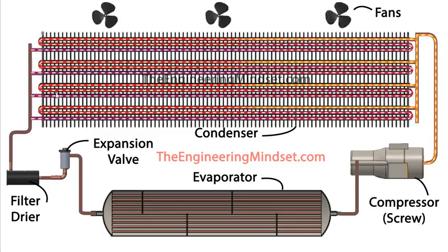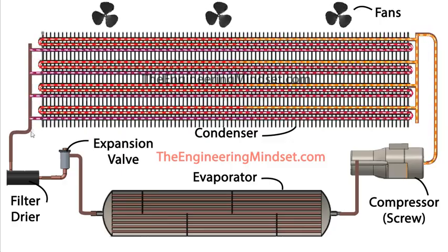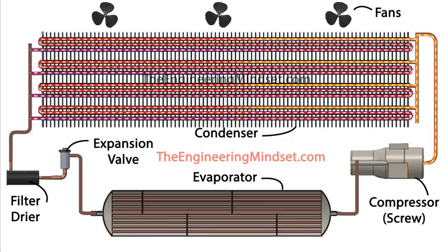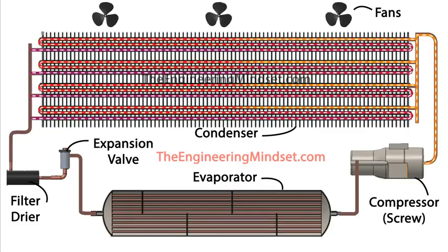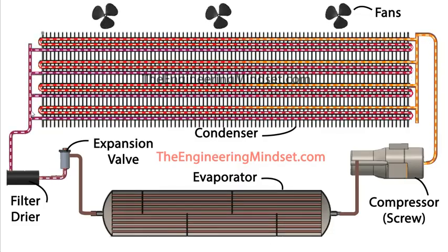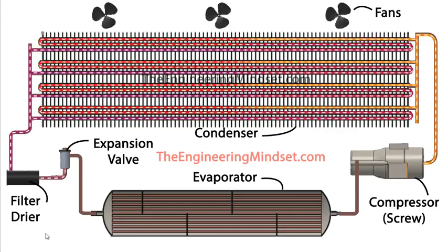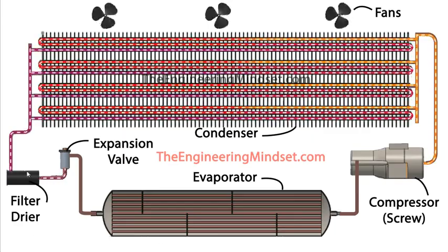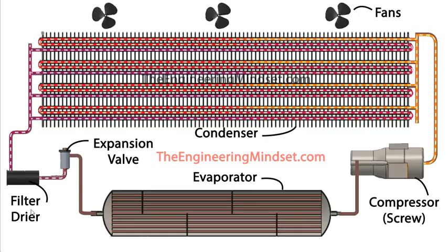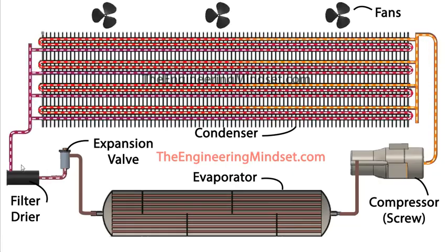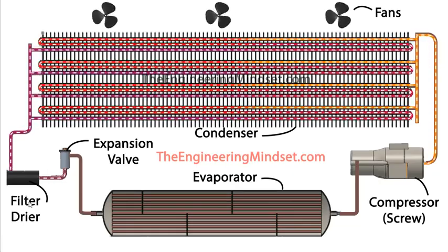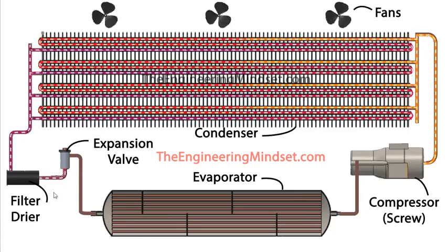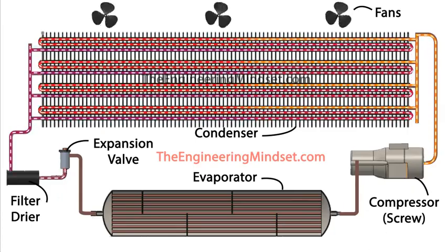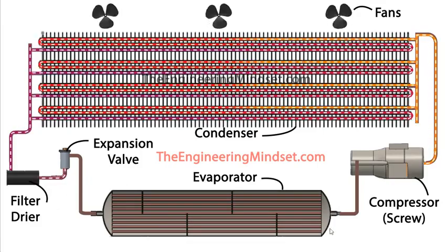By the time the refrigerant leaves the condenser at these points here, that should all be a high pressure, medium temperature, saturated liquid. That refrigerant will then make its way through this collection header and down towards the filter dryer. Now the filter dryer really just absorbs any water, because the water would become like an acid, so it stops that passing through. It will also filter it a bit, getting out oils and things like this to stop them making their way into the compressor. So once it's passed through there, it will then make its way up into the expansion valve.